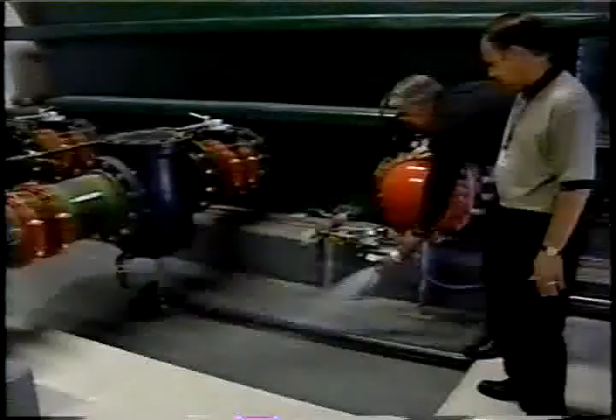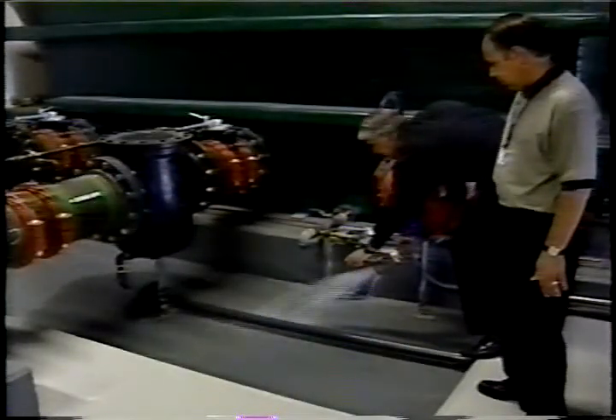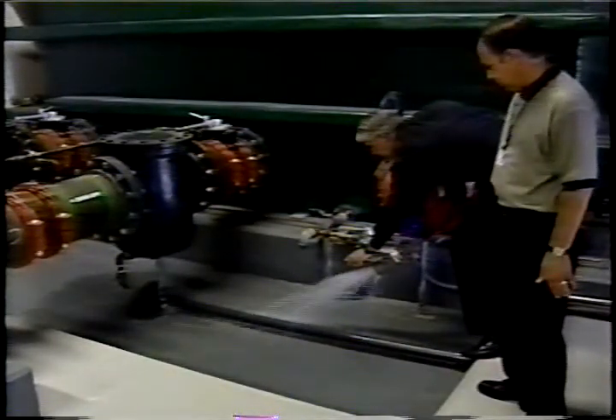The tower waters are flushed only once every 4 hours, for only 3 minutes at a time. That means instead of water going down the drain the old way 48 times a day for 12 hours, now it's down to 6 times a day for a total of only 18 minutes.